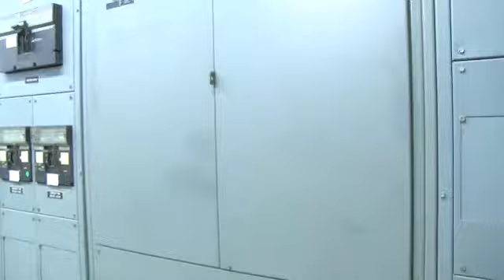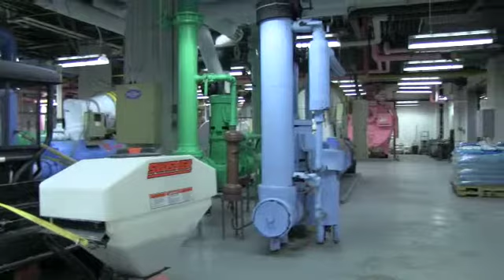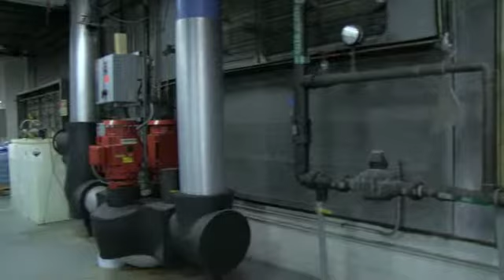The generator takes, good question, no. In case you're interested, the question Francie's asking is, if we had an electrical outage, how much of the building does the emergency generator serve? The emergency generator only takes care of emergency lighting, elevators, and fire pumps. That's the only thing. So we don't power the entire building off of that generator. We have a transfer switch here that will switch each of those respective areas I just mentioned, emergency lighting, fire pumps, and elevators, over to that bank, and then we feed those pieces of equipment through the generator power. Basically, in an outage, you just want to have enough electric to get people out of the building safely and to make sure that the elevators are working and the fire pumps are working.